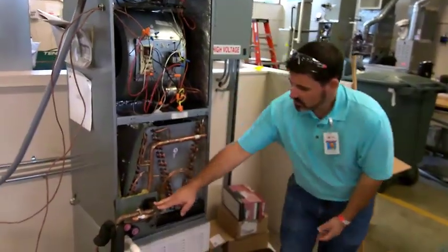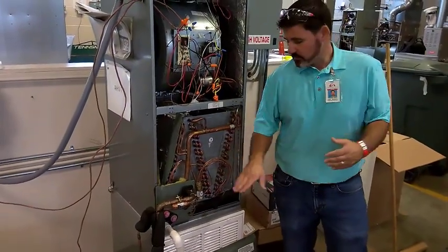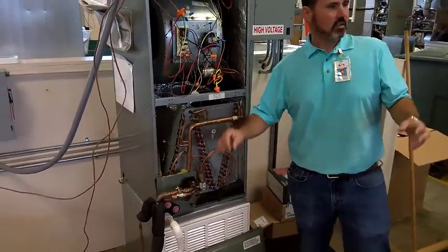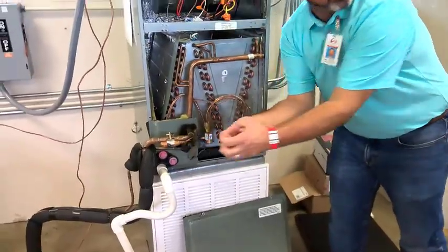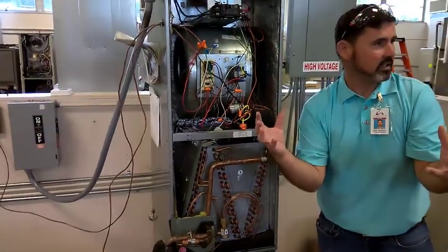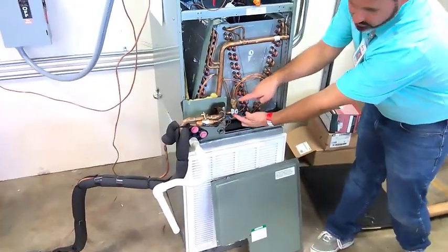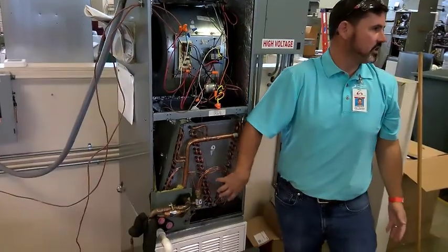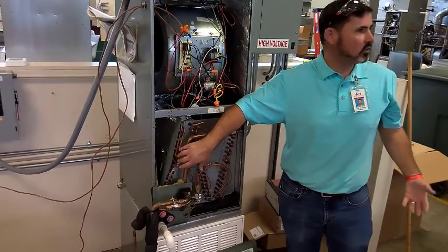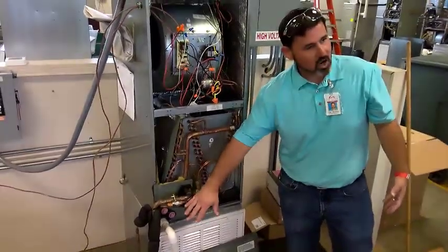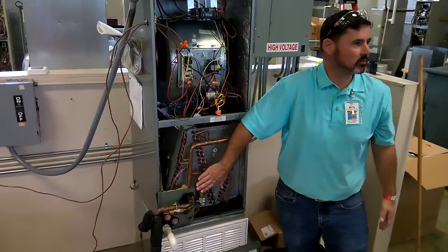All right. Something cool about this metering device is its job as a TXV, thermostatic expansion valve, is to maintain a certain superheat. So if I have a warm coil coming out, this bulb has refrigerant inside of it. If it starts warming up, it's going to expand. It's got to push this disc in, which will open up a needle in there and let more refrigerant in. The warmer this gets, the more refrigerant this thing's going to allow in there. And then if it gets so cool that pressure is going to drop, it doesn't need as much refrigerant. That needle's going to close some more. As that needle closes, I've got less refrigerant going in there.